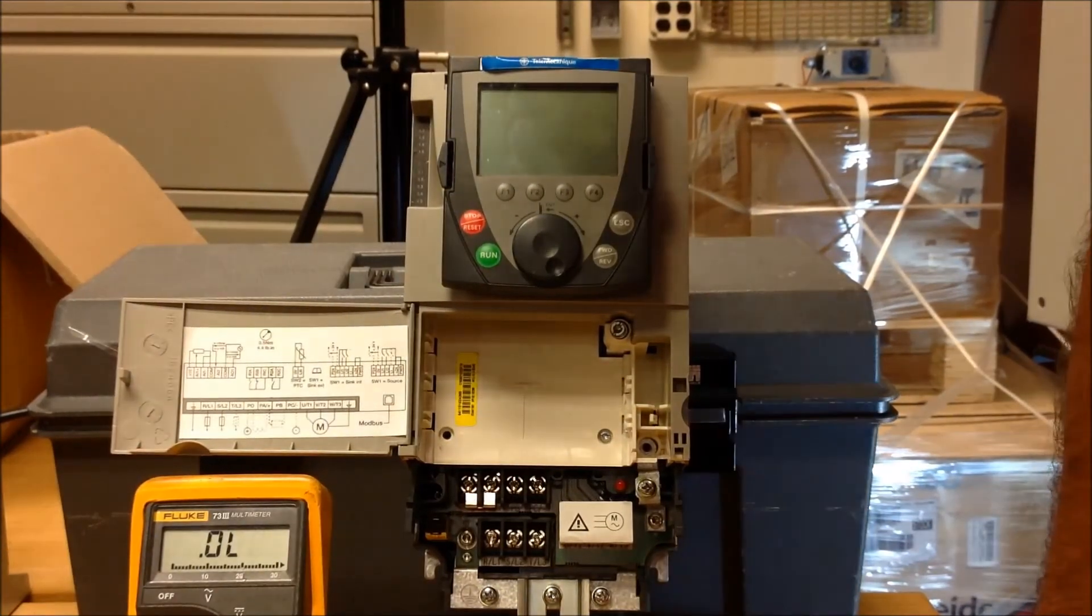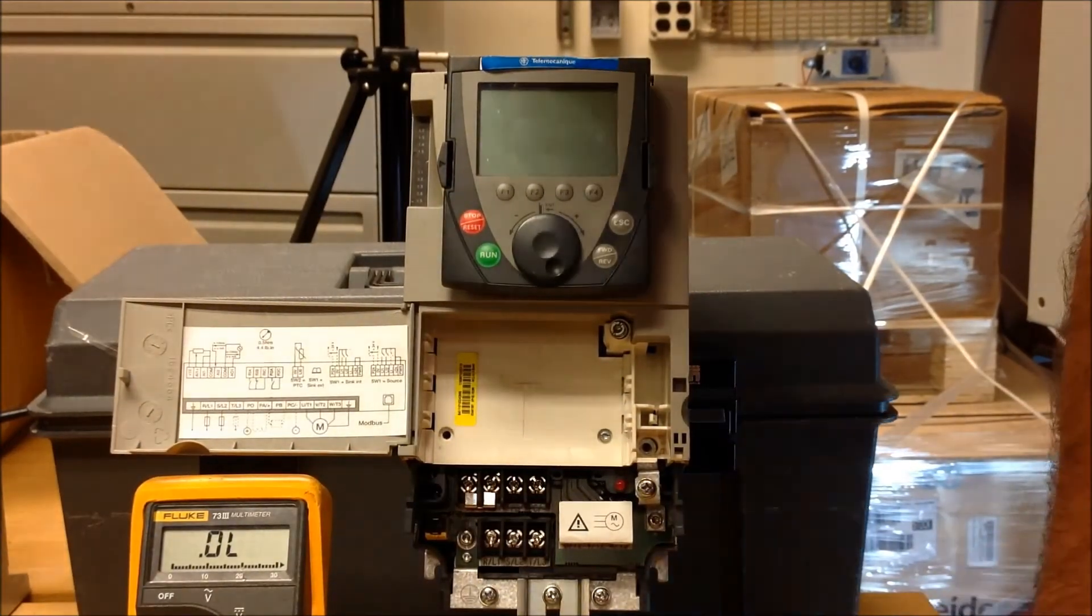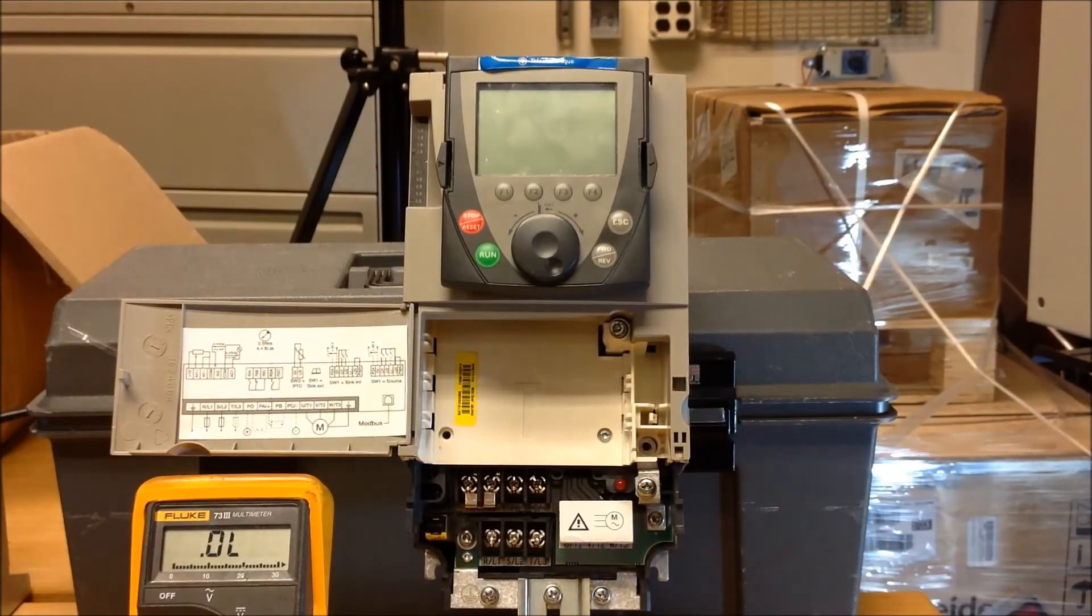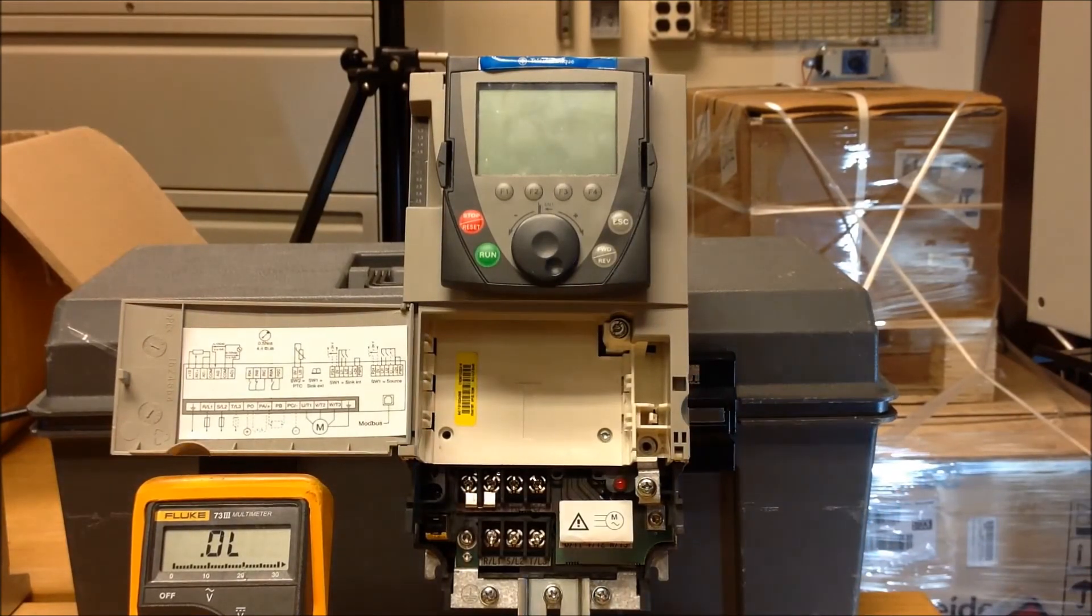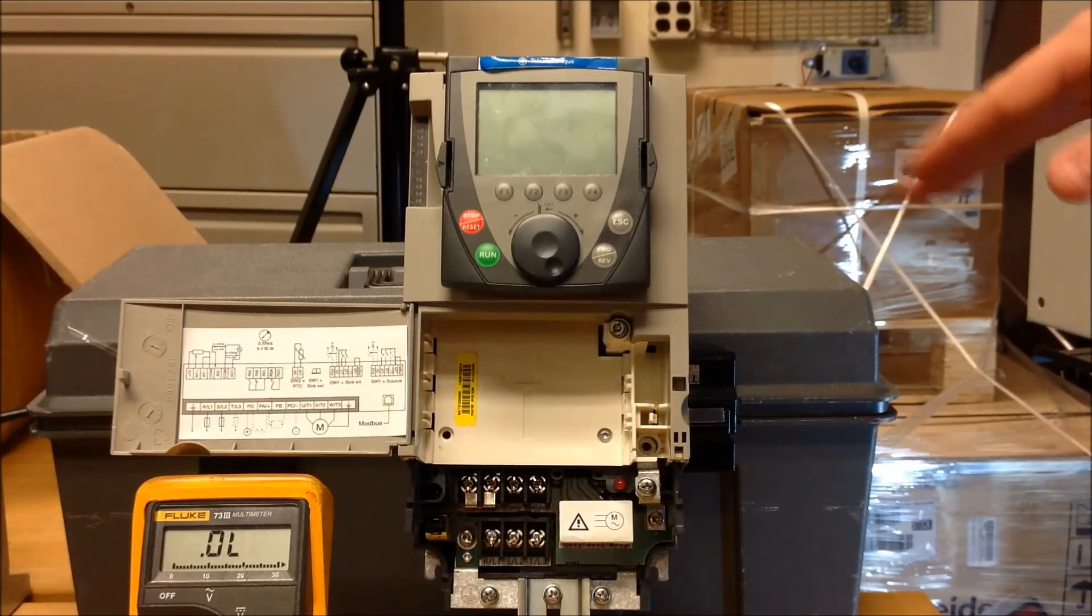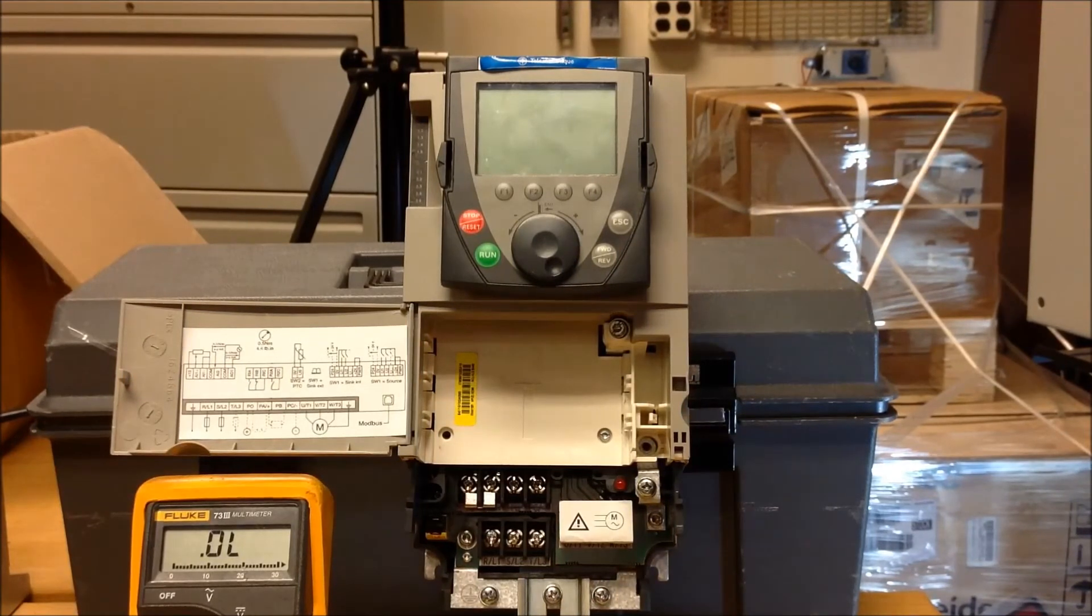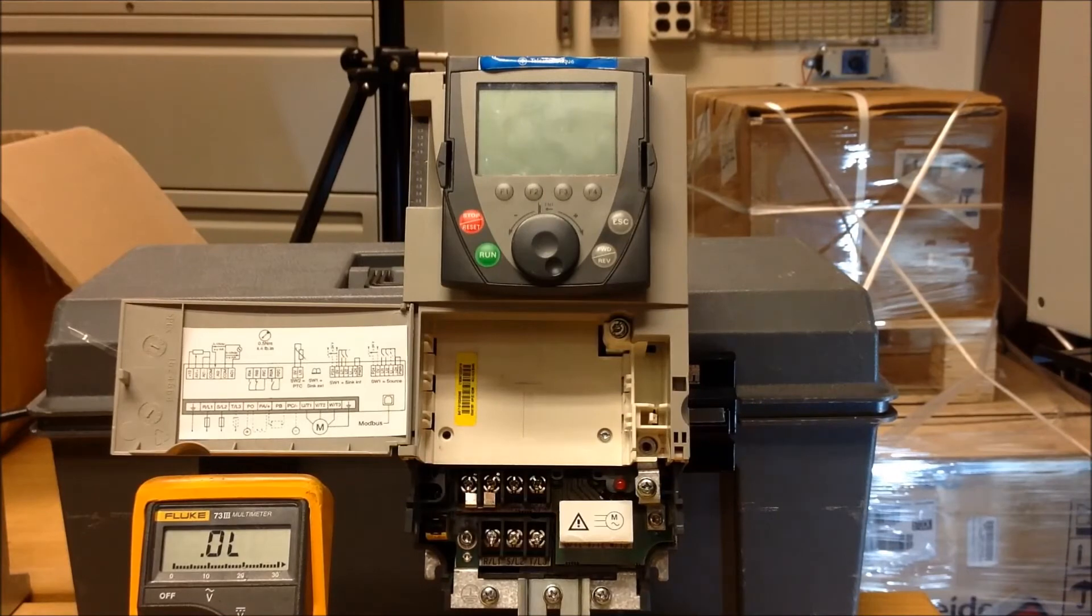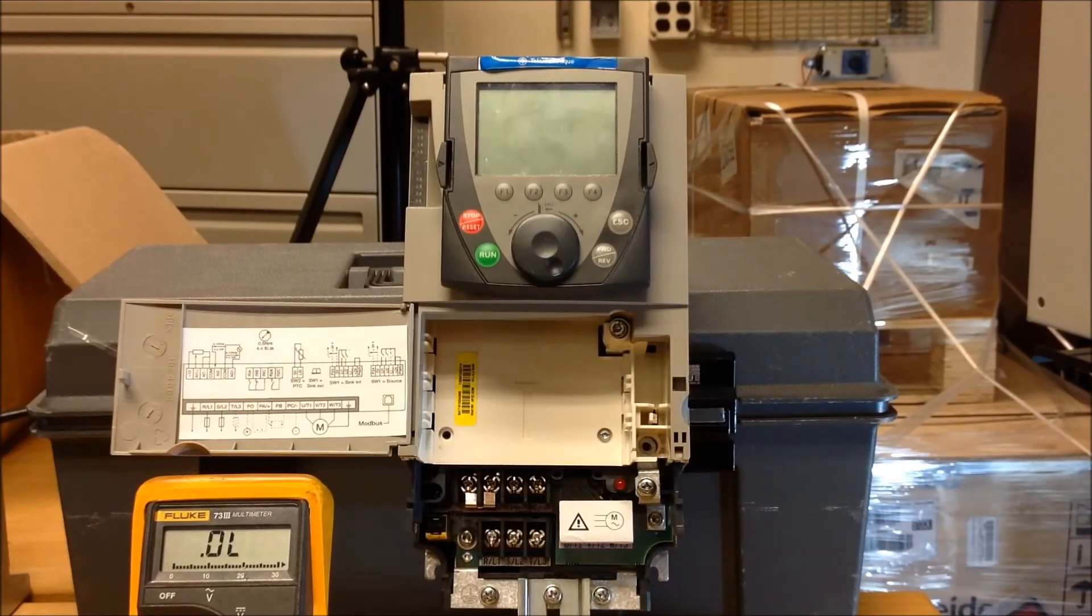Now, those were all on the line side of your drive. So we have done a total of 12 measurements, going from your line terminals to the DC bus, PA and PC in both directions of your meter.